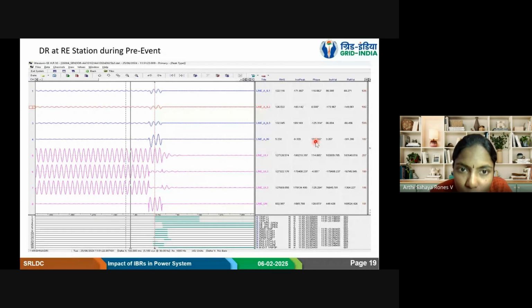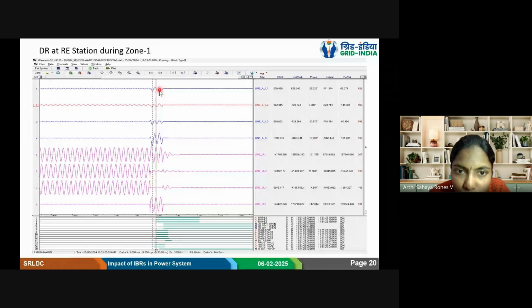But what happened during the fault? Even though it is an RY fault, we are seeing zero sequence current, and also in this case, zone 1 trip we are seeing. Zone 1 is getting tripped. So usually when we talk in terms of current, for zone 1 to operate, sufficient fault current should be there. But in this case, fault current is not there. But you see, the voltages have collapsed like anything. It has gone almost to 8 kV, a 230 kV system going up to 8 kV. Because of this, zone 1 is getting maloperated.